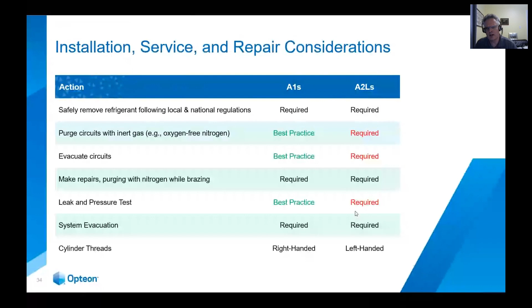Now let's talk quickly about codes and standards in Canada and the US, and how they interact and what those requirements might be. In Canada, we have really two things. We have UL CSA, two standards, 60335-2-89 and 2-40. These are the requirements that the manufacturers use to build their equipment. If I'm building A2L equipment, this gives them information on labeling requirements, fitting requirements, these types of things. Then there's B52, which is the Canadian equivalent to ASHRAE 15 in the US. I say equivalent, it's very similar, and certainly ASHRAE 15 was used as a guide in writing B52, but it really provides information on mechanical rooms and the requirements around installation.